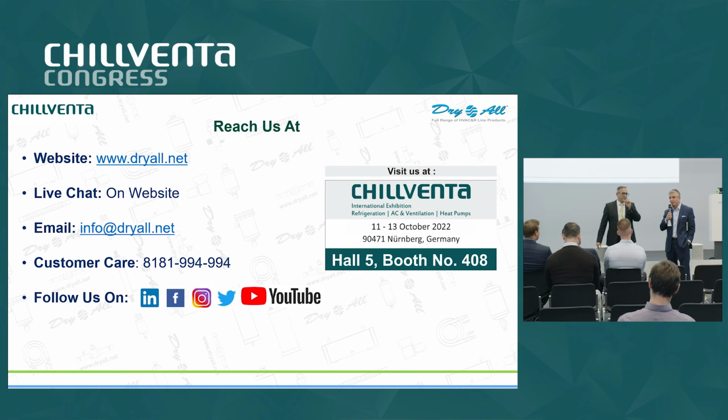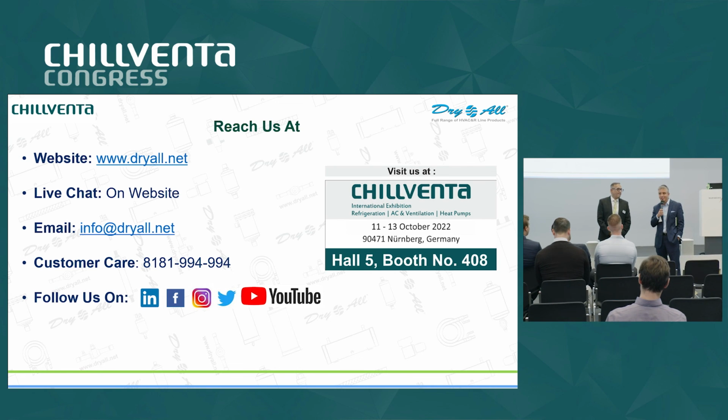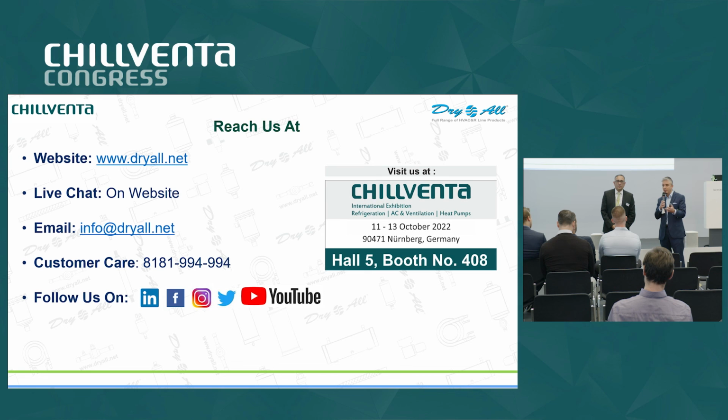The wafers have actually been used in the automotive industry for the last 30 years. Most cars since 1997 have had it as part of the air conditioning system. On the HVAC stationary side, as Vikash mentioned, they are the only company that's integrating it into the receiver dryer. To your question about CO2, yes, because the wafers are inert and they stay within the receiver dryer. They don't melt, they don't fall apart, they don't disintegrate. Essentially, you're pulling the impregnated dye out of the wafer, and the dye takes on whatever properties the system has, which means that it'll work with any oil and any refrigerant. In the electric vehicle market, where they're dealing with very tight tolerances on dielectric resistivity and conductivity, they're looking at the wafer as the only solution for leak detection, precisely because it doesn't affect the system at all.